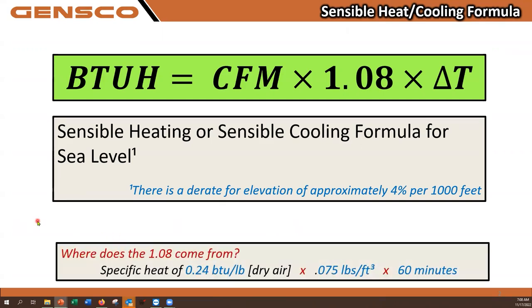And where does that 1.08 come from? It's from the specific heat content of dry air: 0.075 pounds of air per cubic foot of air, because again, we're dealing with CFM, and 60 minutes in an hour, because we are dealing with BTUH, how many BTUs the system produces in an hour.